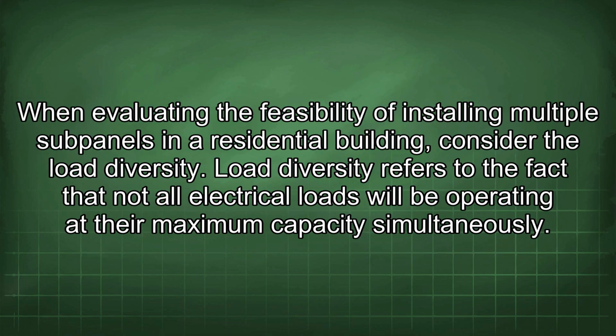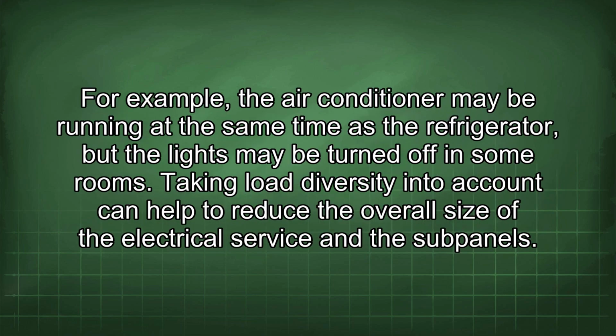When evaluating the feasibility of installing multiple subpanels in a residential building, consider the load diversity. Load diversity refers to the fact that not all electrical loads will be operating at their maximum capacity simultaneously. For example, the air conditioner may be running at the same time as the refrigerator, but the lights may be turned off in some rooms. Taking load diversity into account can help to reduce the overall size of the electrical service and the subpanels.